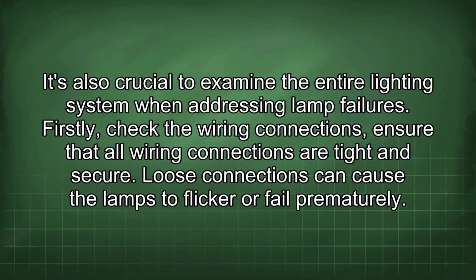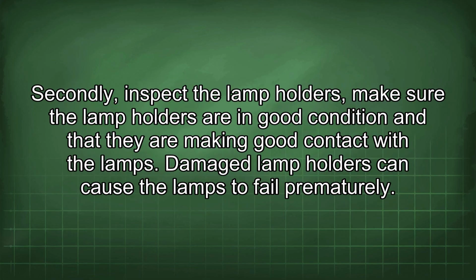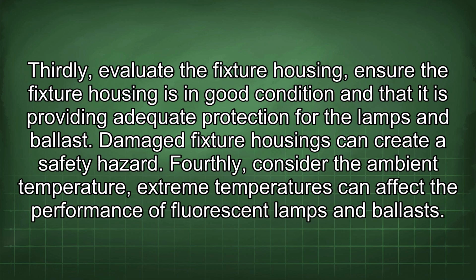Firstly, check the wiring connections. Ensure that all wiring connections are tight and secure. Loose connections can cause the lamps to flicker or fail prematurely. Secondly, inspect the lamp holders. Make sure the lamp holders are in good condition and that they are making good contact with the lamps. Damaged lamp holders can cause the lamps to fail prematurely. Thirdly, evaluate the fixture housing. Ensure the fixture housing is in good condition and that it is providing adequate protection for the lamps and ballast. Damaged fixture housings can create a safety hazard.